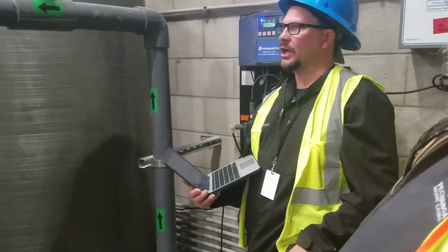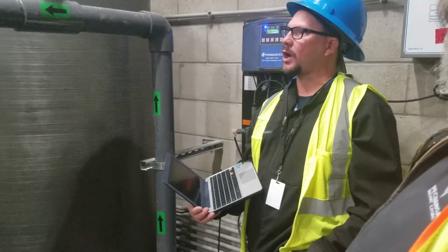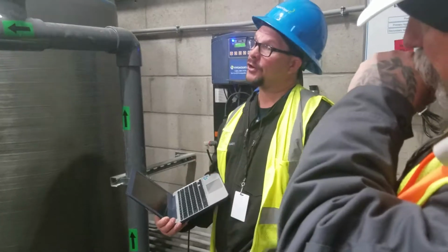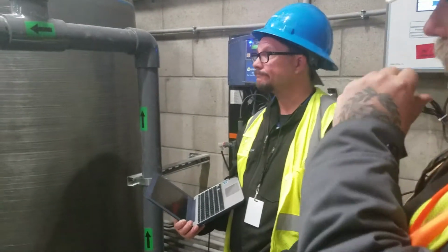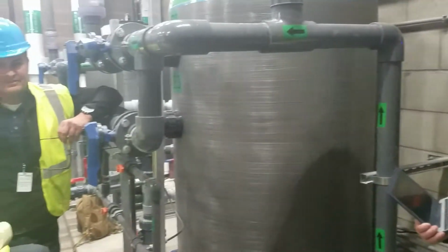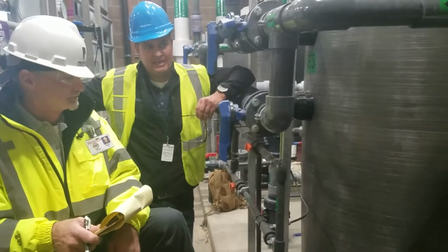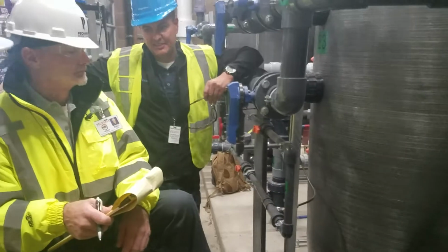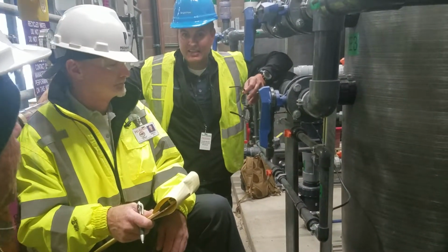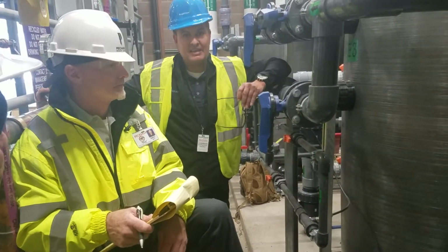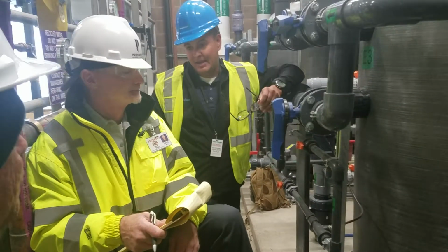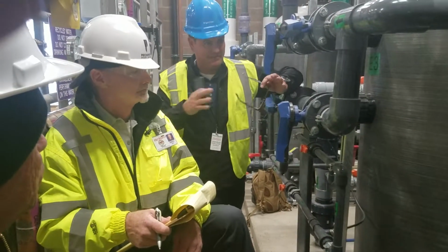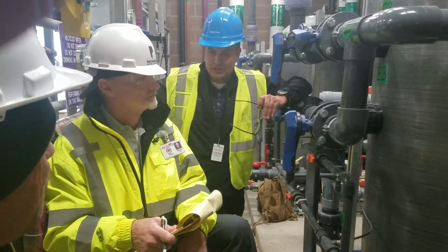If we lose control of the alkalinity, we're going to be chasing pH all day long. It's not going to be fun. And that will affect your chlorine as well. On that 7.3 pH, we typically run commercial facilities now on the low range of pH. The reason is the increase in waterborne disease, the Legionella outbreaks and things like that we're seeing. So the lower we run the pH, the stronger the chlorine. Instead of running an aggressive 7.4 to 7.6, we'll run a 7.3 to a 7.5, and keep it in that lower range for the strength of the chlorine.